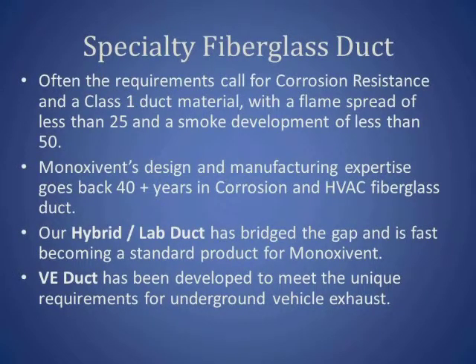Specialty fiberglass duct often requires corrosion resistance and a Class 1 duct rating for flame and smoke spread. Monoxivent's design and manufacturing expertise goes back 40 plus years in both the corrosion market and the HVAC fiberglass duct market. Our hybrid or lab duct, which we're going to emphasize today, bridges the gap between these two product lines, but it's fast becoming a standard for us. Another specialty duct that we've developed is our VE duct to meet the unique requirements for underground vehicle exhaust.